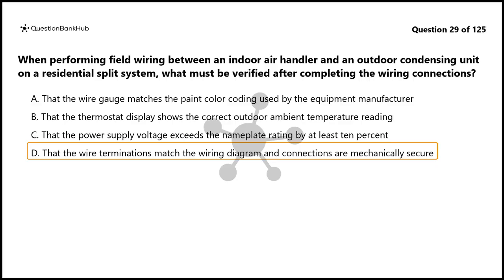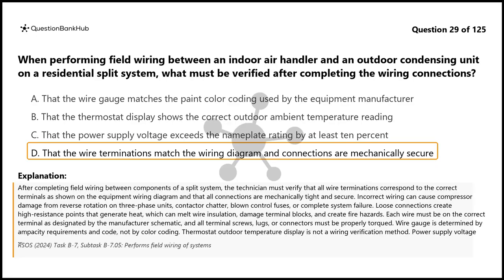The correct answer is D. After completing field wiring between components of a split system, the technician must verify that all wire terminations correspond to the correct terminals as shown on the equipment wiring diagram and that all connections are mechanically tight and secure. Incorrect wiring can cause compressor damage from reverse rotation on three-phase units, contactor chatter, blown control fuses, or complete system failure. Loose connections create high resistance points that generate heat, which can melt wire insulation, damage terminal blocks, and create fire hazards. Each wire must be on the correct terminal as designated by the manufacturer schematic, and all terminal screws, lugs, or connectors must be properly torqued.